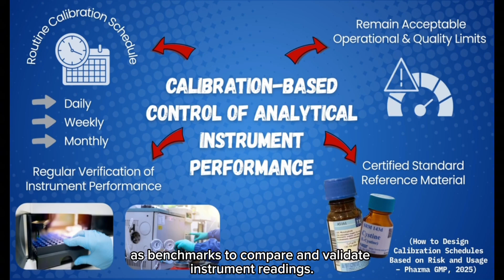On calibration-based control of analytical instrument performance, the laboratories should implement daily, weekly, and monthly routine calibration schedules to ensure that instruments are regularly monitored and continue to function accurately over time. Next, regular verification is performed before analytical testing to confirm that the instruments are properly operated and are suitable to be used. In addition, calibration ensures that laboratory instruments remain within acceptable operational and quality limits. Finally, certified standard reference materials are used during calibration procedures as benchmarks to compare and validate instrument readings.